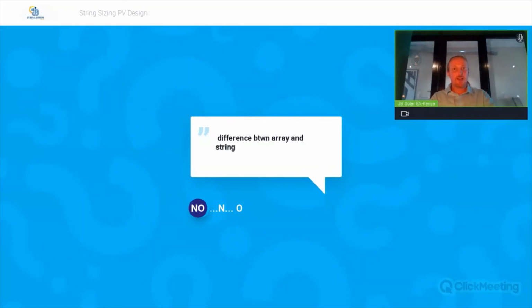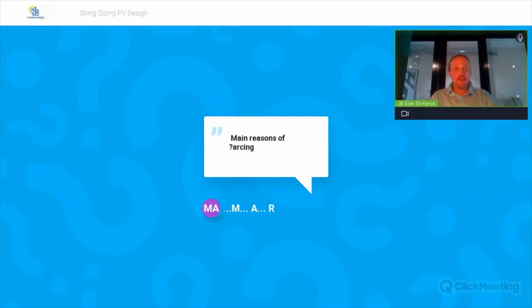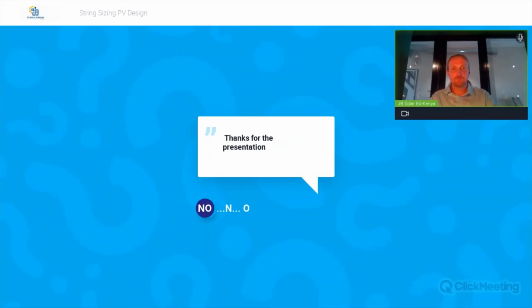Difference between array and string. I think I've answered this. Generally, an array is many strings, and a string is the panels connected in one series. Main reasons of arcing. Okay, arcing. We didn't talk about arcing today. The main reasons are a faulty connection or a damaged wire, but we talk about that in another webinar because we have arc fault protection. So there's another webinar for this.